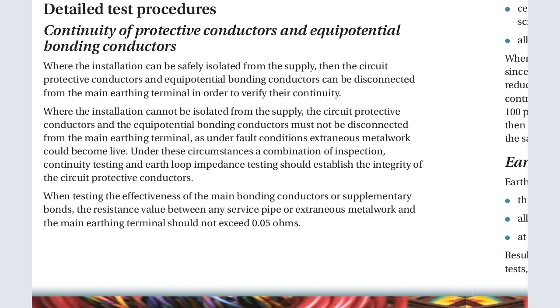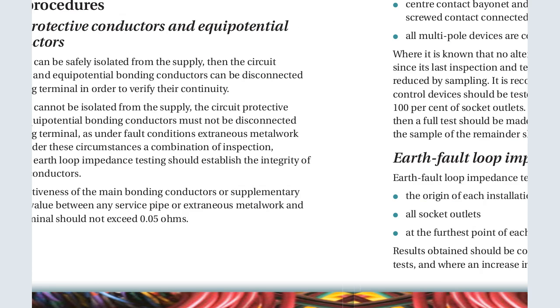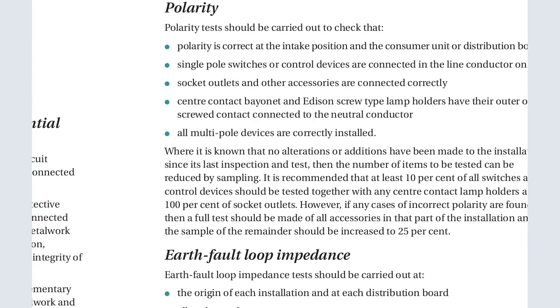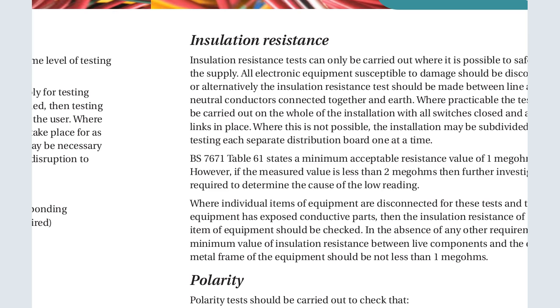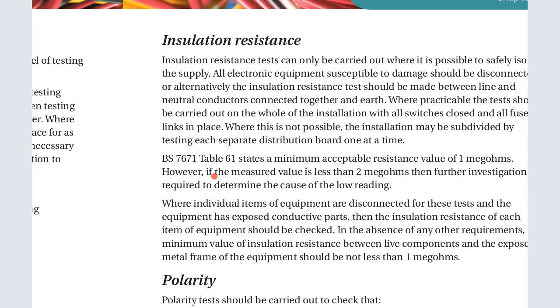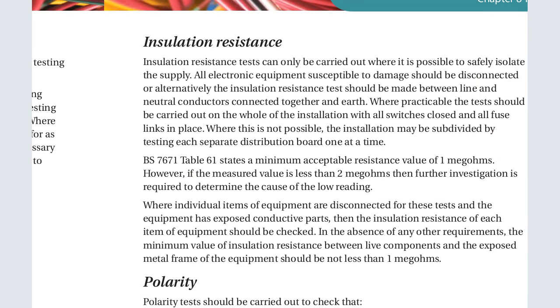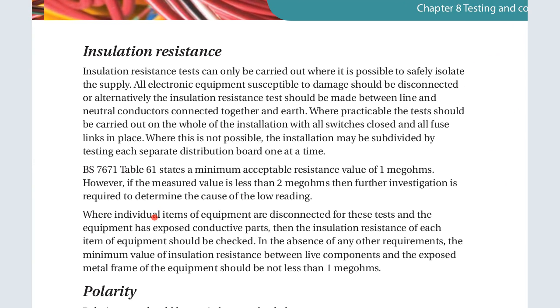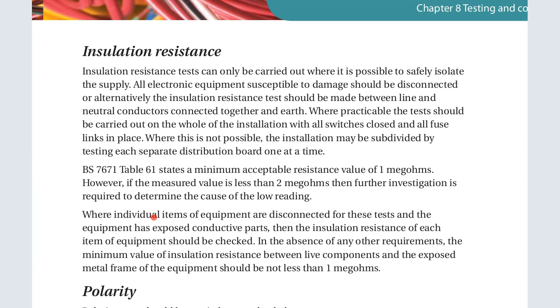When testing the effectiveness of the main bonding conductors or supplementary bonds, the resistance value between any service pipe or extraneous metalwork and the main earthing terminal should not exceed 0.05 ohms. That is a requirement. And then we have another test called the insulation resistance test. So number one, we said the continuity test. Number two is the insulation resistance test. An insulation resistance test can only be carried out where it is possible to safely isolate the supply.